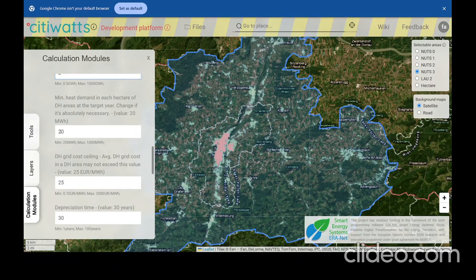Additionally, you have the option to increase the threshold for the hectare cells in order to limit your obtained district heating areas. The higher this value, the smaller the region that you get. So if you are planning to see the maximum potential, then it's better not to change this value. But if you are planning to cherry pick only the areas with very high heat demand, maybe you need to adapt this value as well.